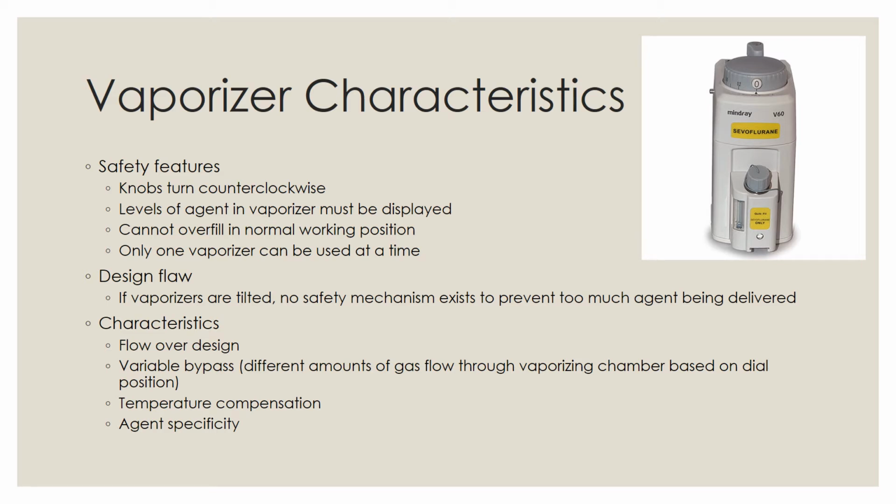So some characteristics of modern vaporizers, they're all flow over design. This is in contrast to bubble through. The fresh gas flow flows into a vaporizing chamber where the liquid agent is evaporating into the air above it. The fresh gas picks up the evaporated agent and carries it off. This is in contrast to bubble through, which is like the old copper kettles, where fresh gas was actually bubbled through agent and picked up that way.